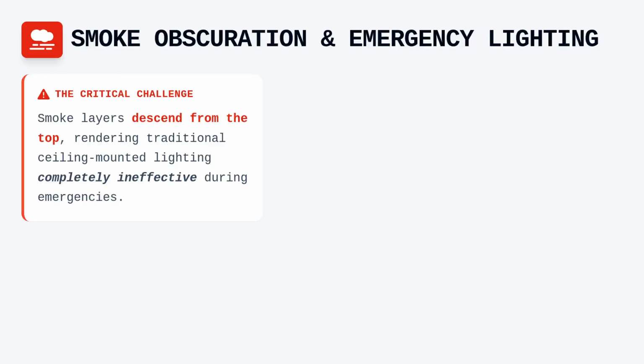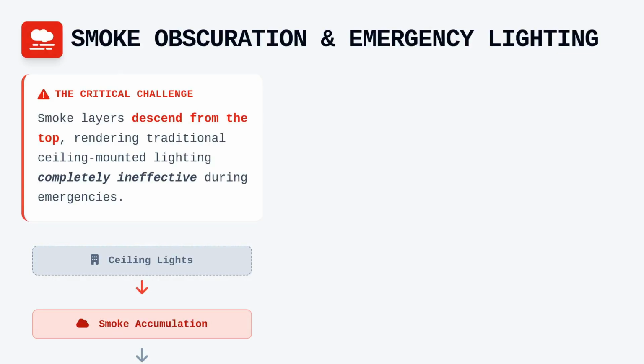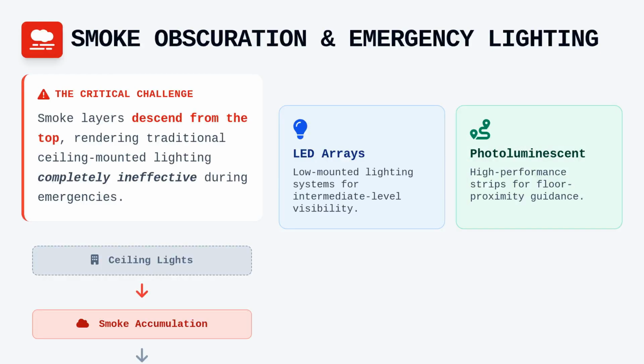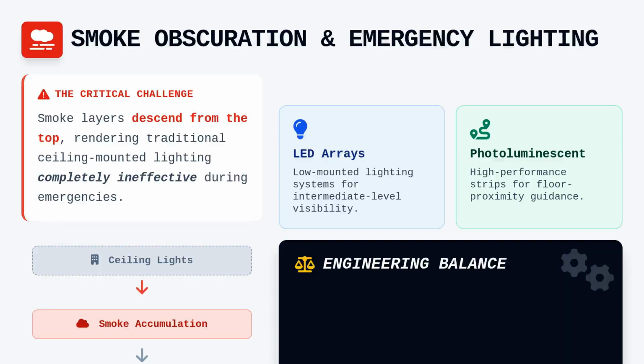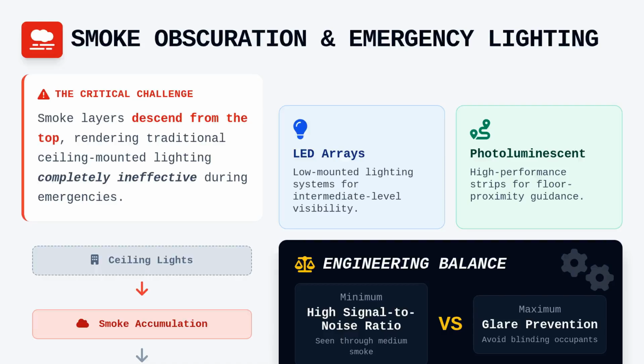Smoke obscuration presents a significant challenge to traditional ceiling-mounted emergency lighting, as smoke layers naturally descend from the top of an enclosure. In spaces where smoke accumulation is likely, floor proximity pathway markings or intermediate-level lighting systems become necessary to maintain visibility when the upper atmosphere is obscured. These systems utilize low-mounted LED arrays or high-performance photoluminescent strips to guide occupants when visibility distance at eye level is reduced below functional thresholds. The challenge here is to ensure that the light output from these devices does not create intense glare that blinds occupants while they're crawling or moving in low visibility conditions.